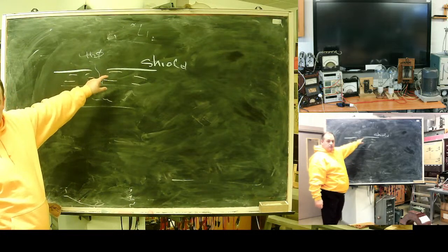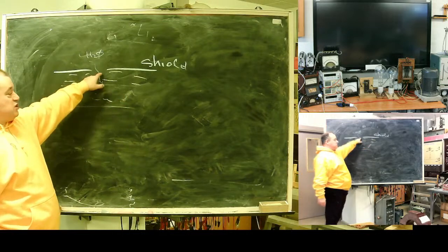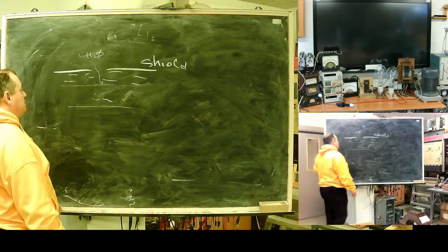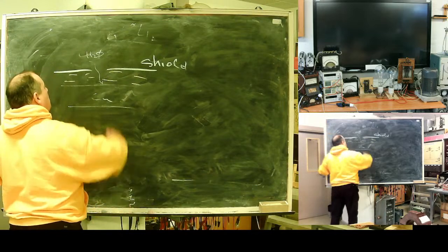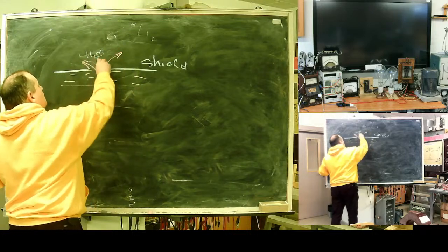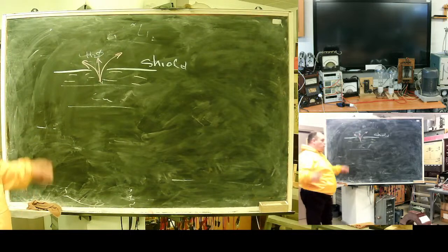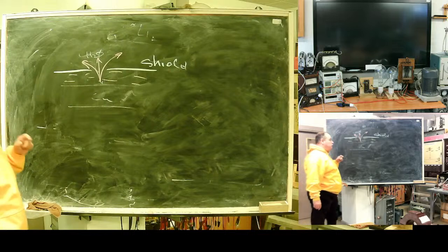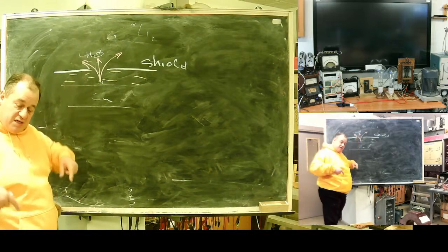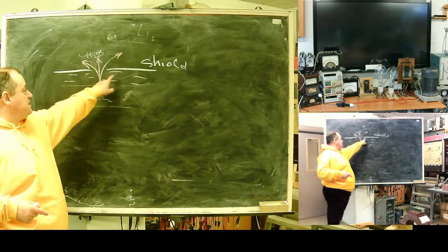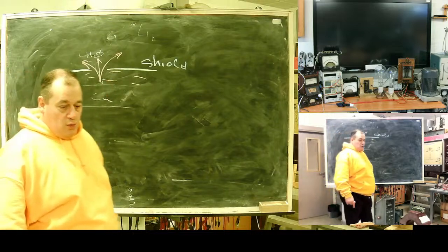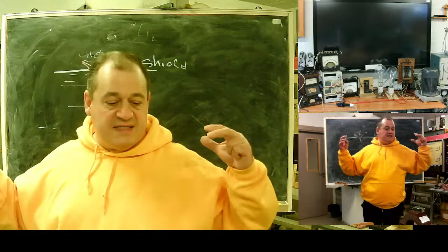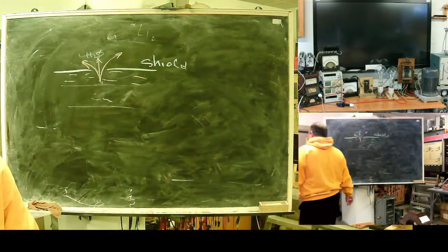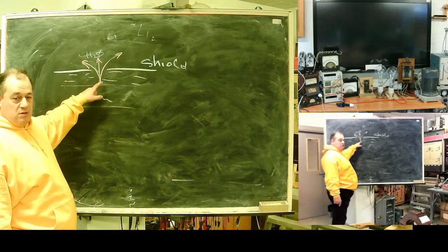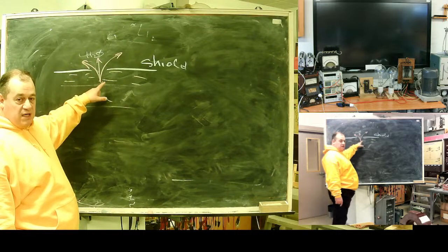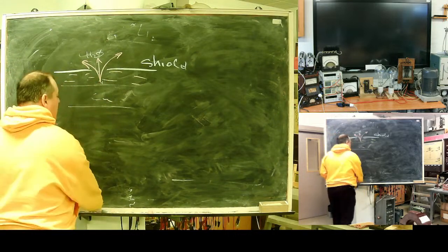Earth fault. What happens during Earth fault? All the network capacitance discharges through this place. High current causes what? Heat effect. And all this mixture of water and oil been thrown out. Sometimes what happens, at first moment it breaks through. Heat effect of current causes this cable wax to melt, and seal the place of fault. But if it shells out, it throws out conductive elements, water and what else, and insulation returns for some time.